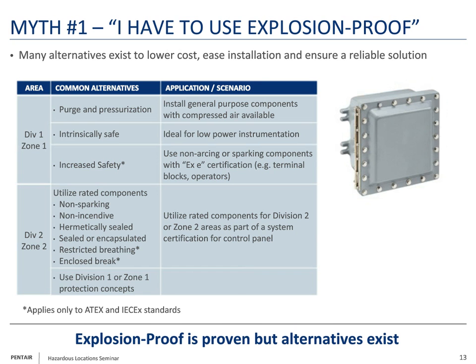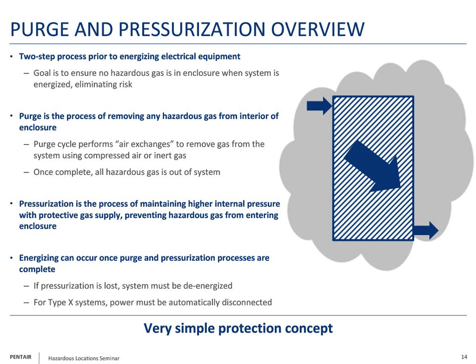Purge and pressurization, we've referred to this a lot already. It's a very simple protection concept. You're just taking compressed air or inert air and putting it into an enclosure to keep hazardous gas out. So it's a two-step process. The first step is purging, which removes the hazardous gas from the interior of the enclosure.